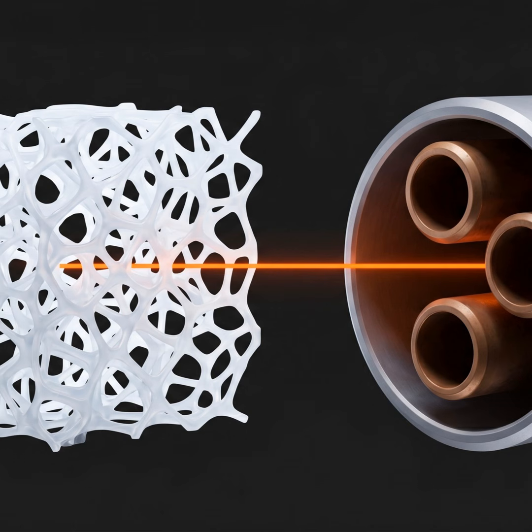First, let's look at the boiler room down in the basement. Okay. Because you are now preheating, or entirely heating, that processed water using the waste heat scavenged from the compressor, the facility suddenly has a massive supply of 140 to 160 degree water for effectively zero cost. They just inherited an unlimited supply of free hot water. Yes. And the immediate result is that their natural gas consumption at the boiler drops drastically. In some optimally sized facilities, the boiler might shut off entirely during production shifts. That is huge. It's an immediate, massive slash to their operating expenses, directly impacting their bottom line.